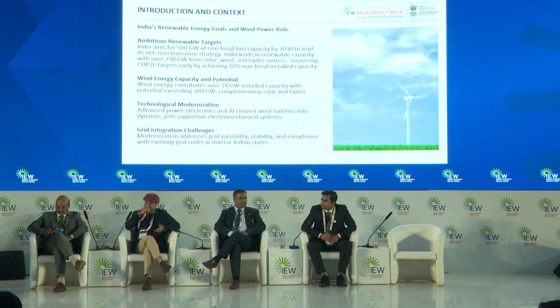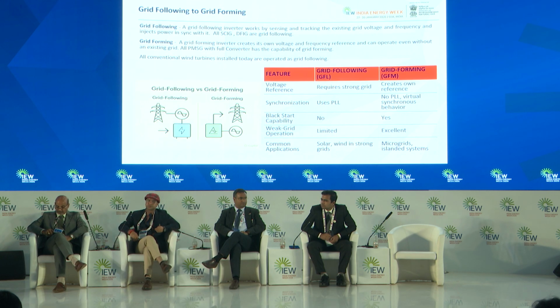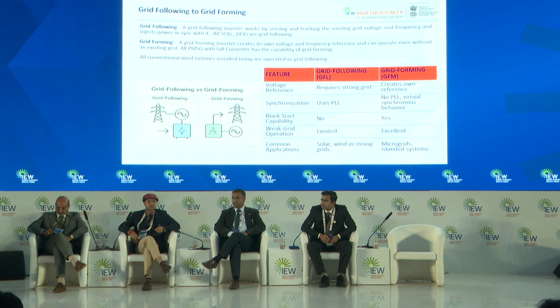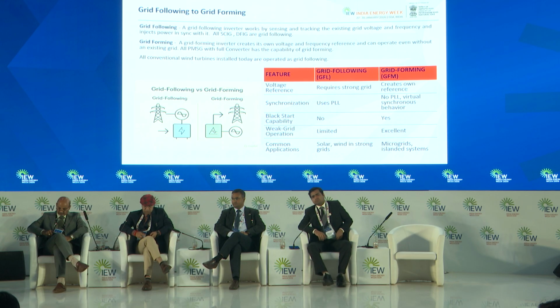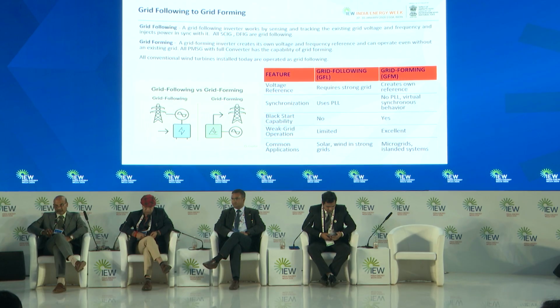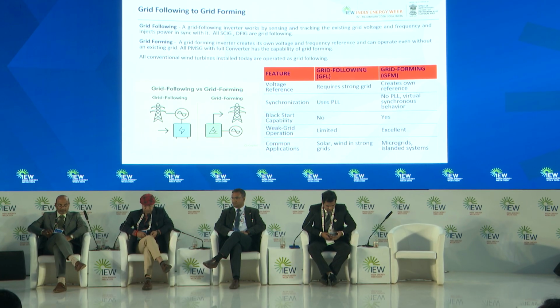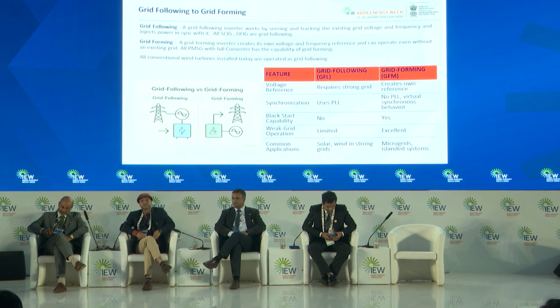Getting into the different operating modes: there are two types — grid following and grid forming. Grid following is where the inverter installed near the wind turbine checks the grid voltage and frequency, aligns to it, and injects power. Grid forming is where the inverter is capable of generating its own voltage and frequency reference and can take the load upon itself, rather than being dependent on the grid to connect to. Some major features, like black start capability, are very important for grid-forming generators, but are not available in conventional wind turbines or generators used in today's technology.